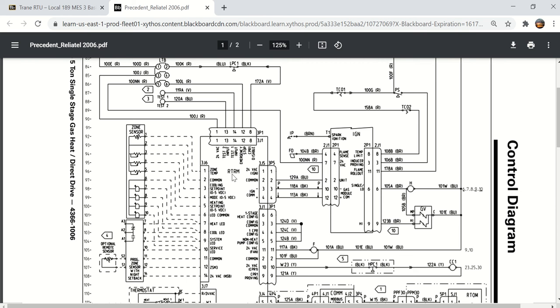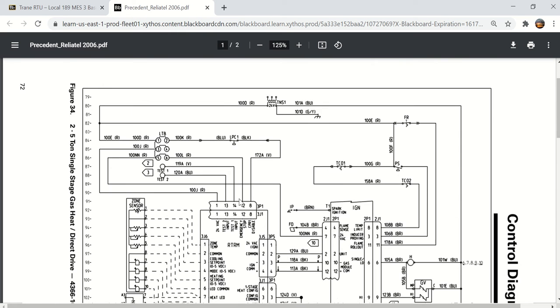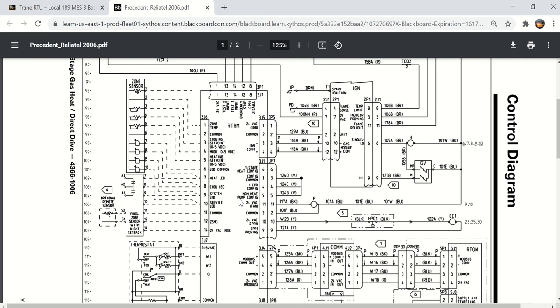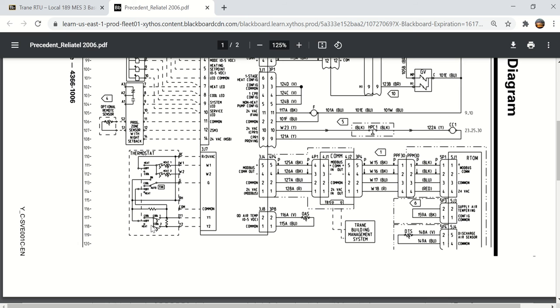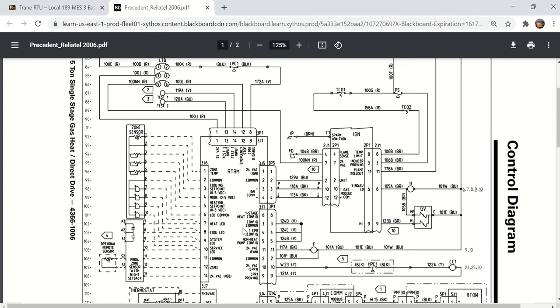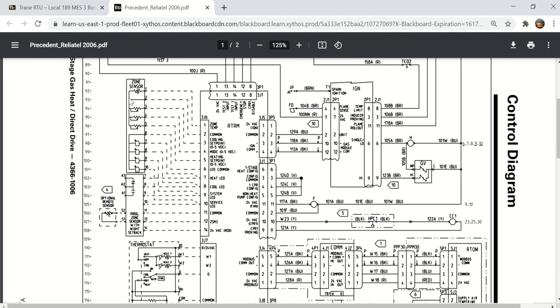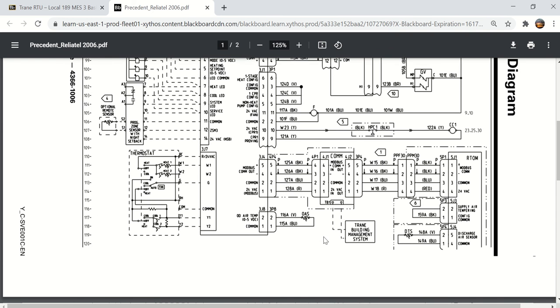One of the things about the RTRM board here was that this, I believe, came out in 2005, 2006 on Trane units. It was called the Reliatel board. Prior to that, all of the Trane smaller rooftop units did not have the inputs for a conventional thermostat like you see right here. You had to buy a conventional thermostat adapter board to adapt to the Trane rooftop unit board. But when the Reliatel board came out, it changed that. You could use either the Trane zone sensor, or you could use a conventional thermostat right to the Reliatel board.